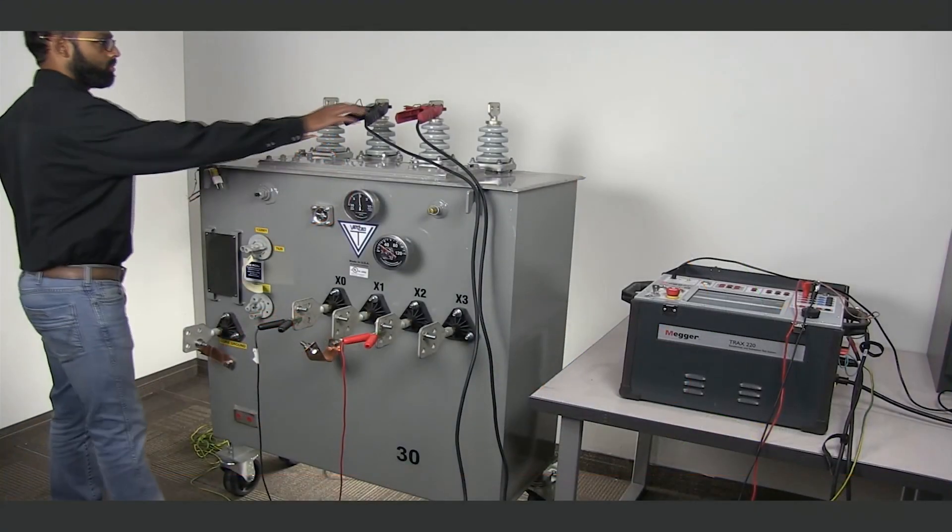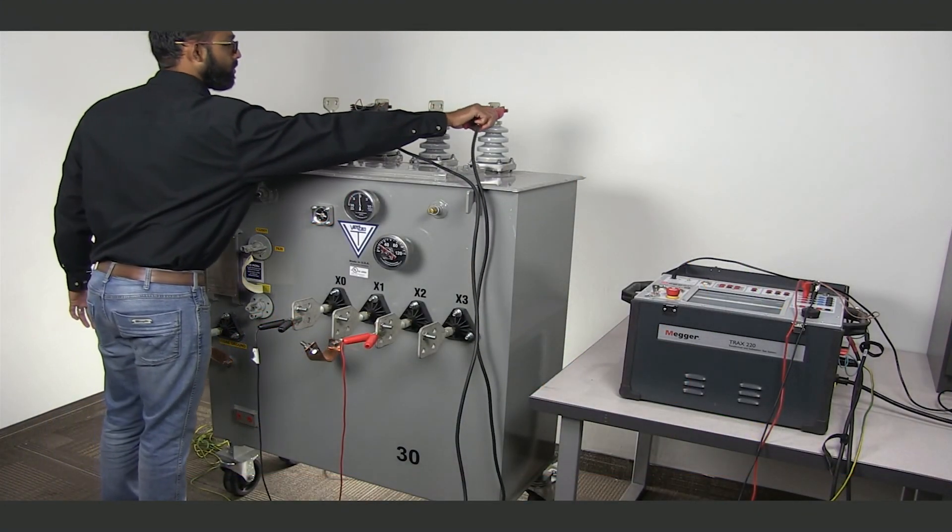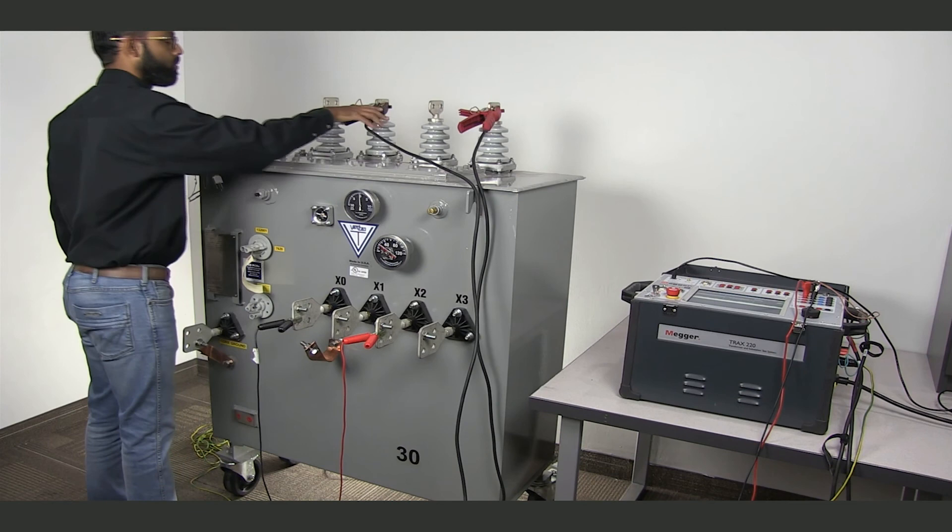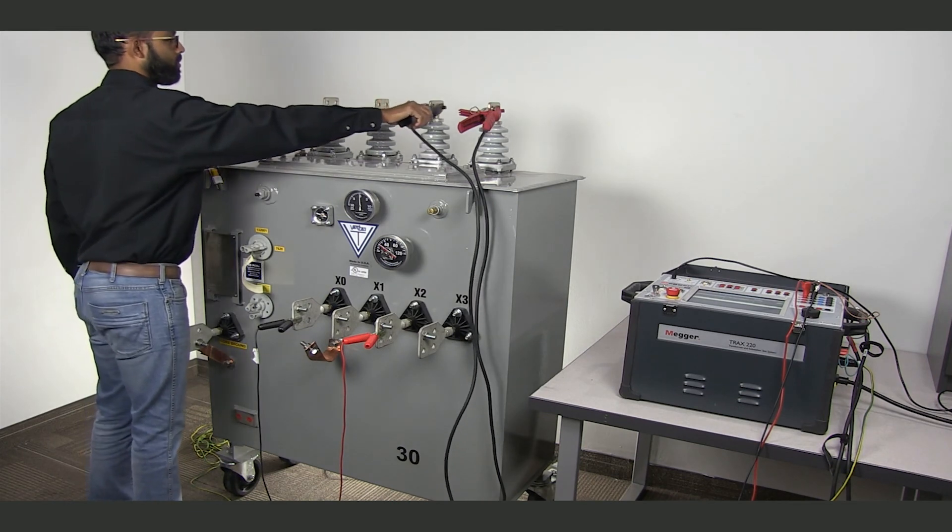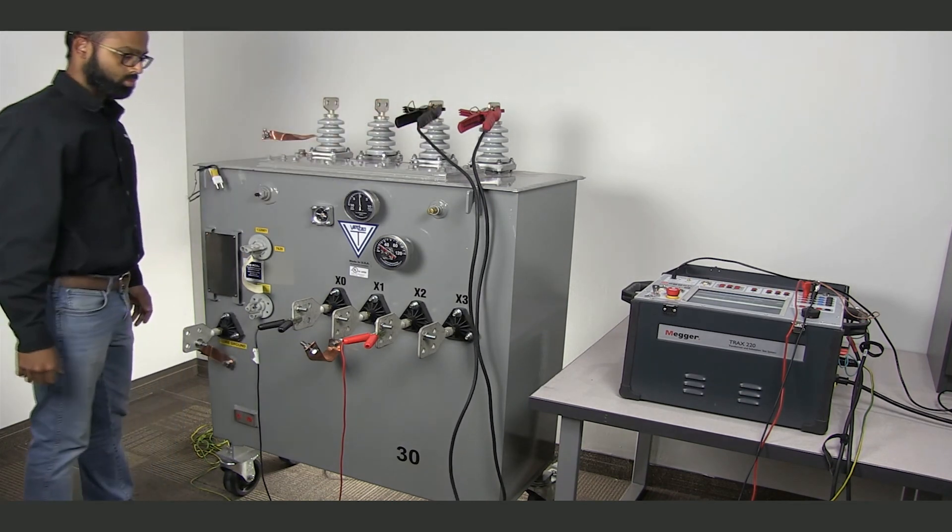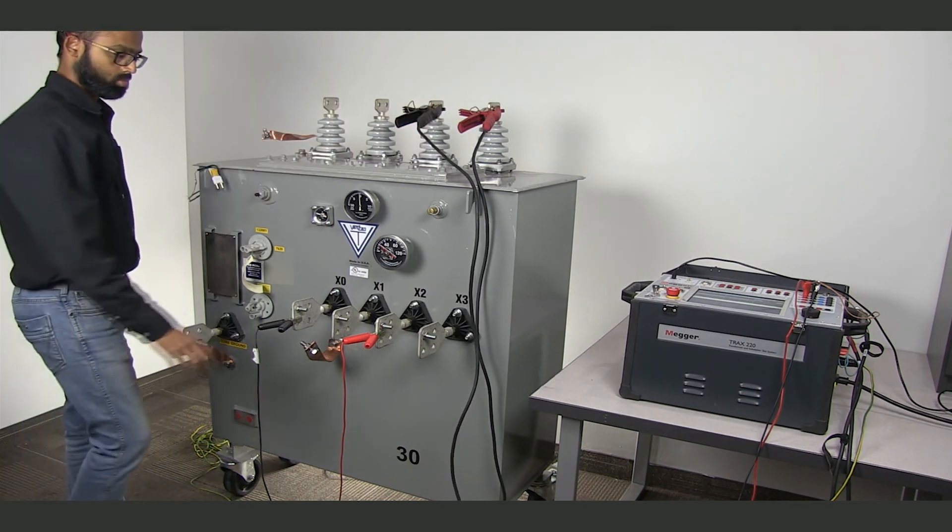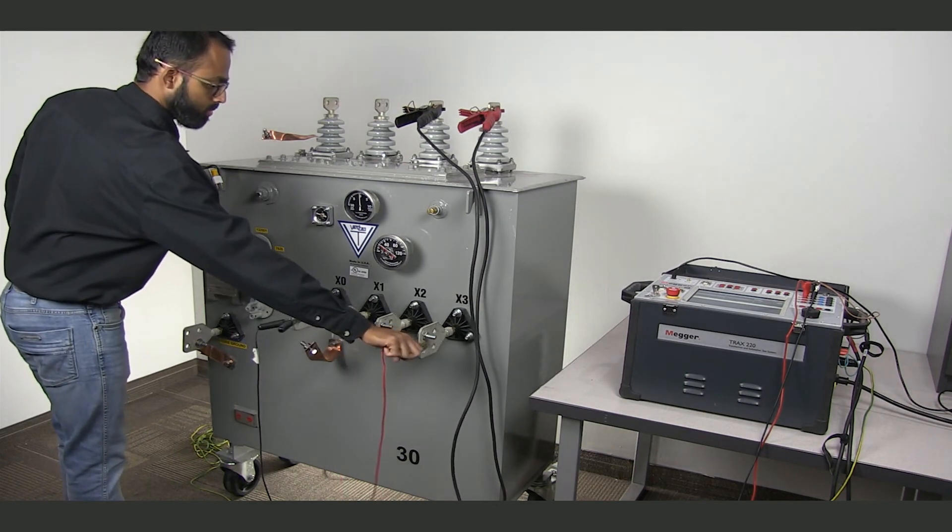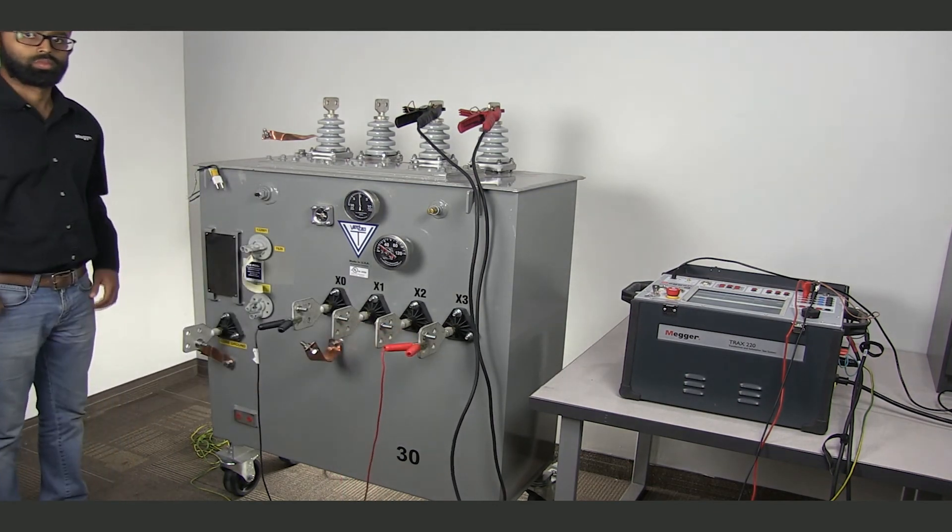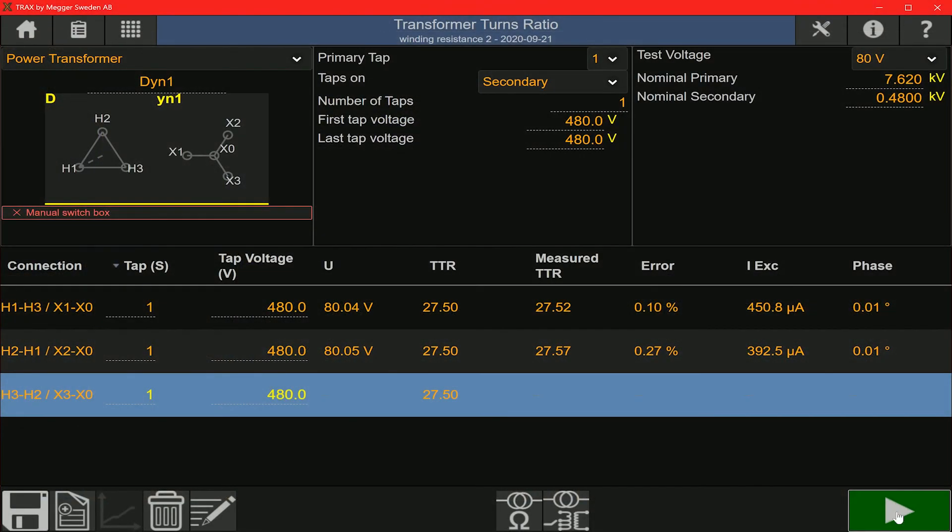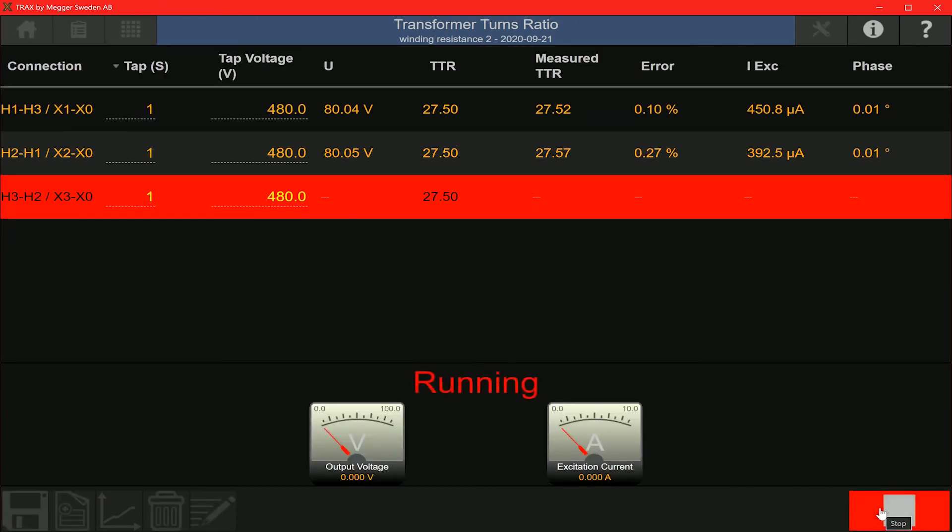To test the C phase, the Kelvin cables are now connected on the H3 and H2 bushings and the red sense cable is moved from the X2 bushing to X3 bushing. Now let's run the measurement on the C phase.